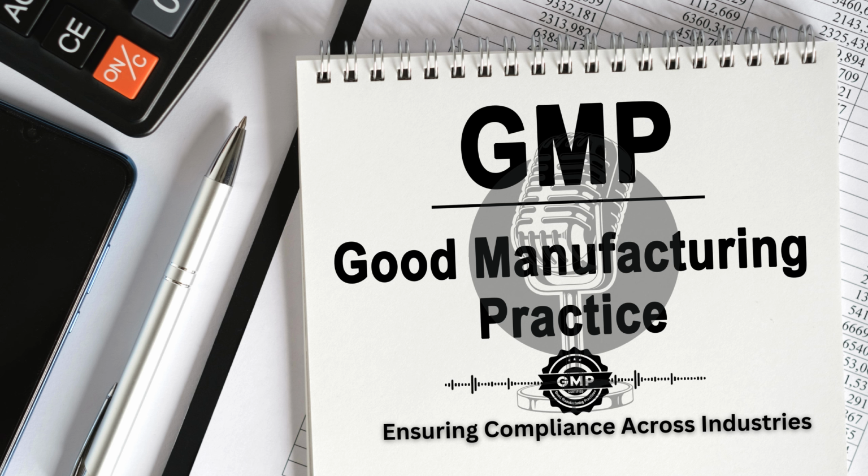Yes, they do. Medical device manufacturers operate under a similar set of quality system regulations that are essentially GMP principles specifically tailored and adapted for the unique characteristics and risks associated with medical devices. For instance, here in the U.S., the FDA has its own comprehensive set of regulations specifically for medical devices, known as 21 CFR Part 820. Think of this as the FDA's specific instruction manual for ensuring quality in the design, manufacture, and control of medical devices. Makes sense. In addition to this, there's also the internationally recognized standard ISO 13485.